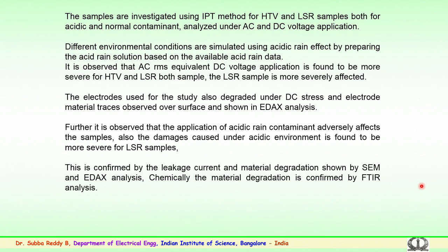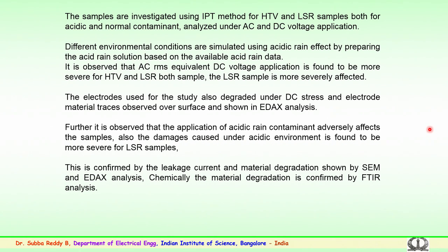Different environmental conditions were simulated using the acid rain effect as per data available in the literature. It was observed that during experimentation, both for AC and DC — where AC RMS equivalent was assumed for DC voltage application — DC stress was found to be more severe, particularly for both the HTV and liquid silicon rubber samples. In the case of liquid silicone rubber, the effect is much more severe. The electrodes used were also seen to be degraded under DC stress compared to AC stress.